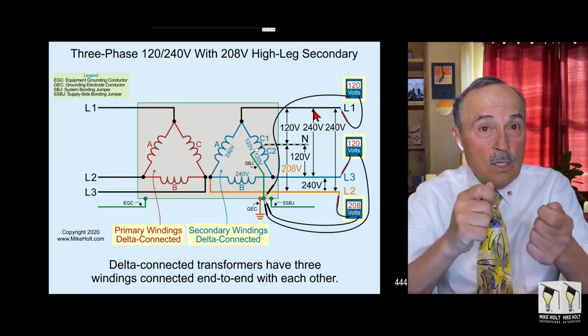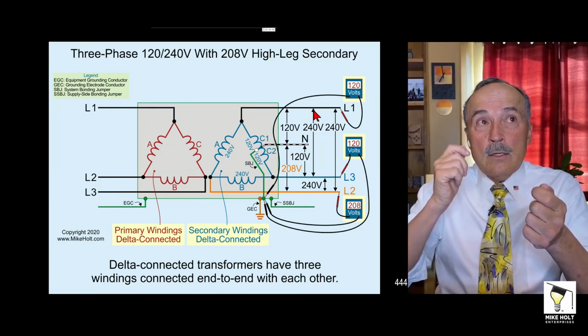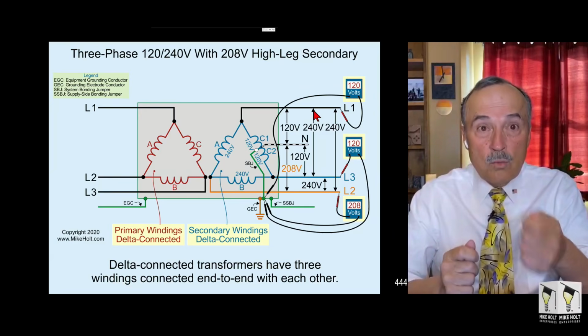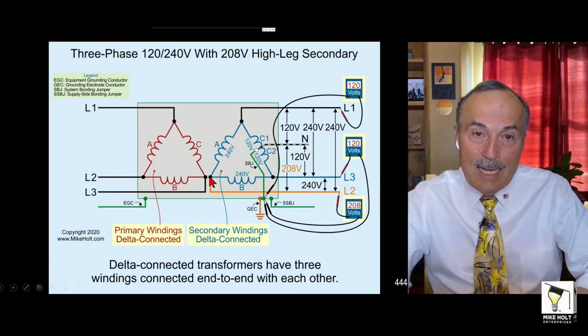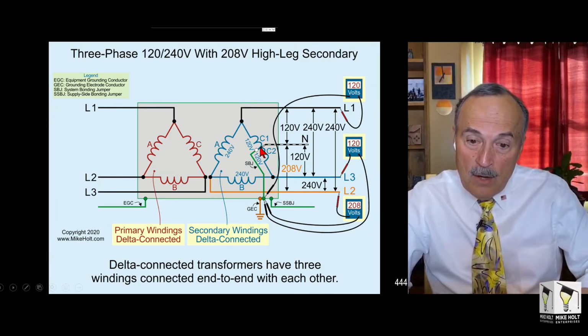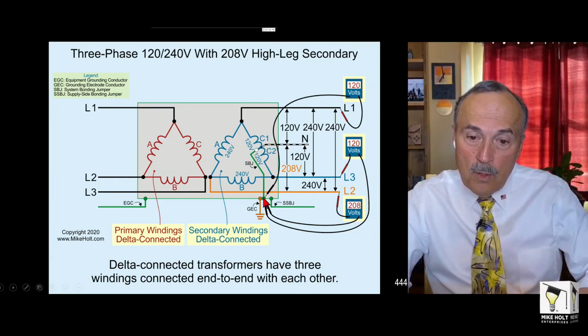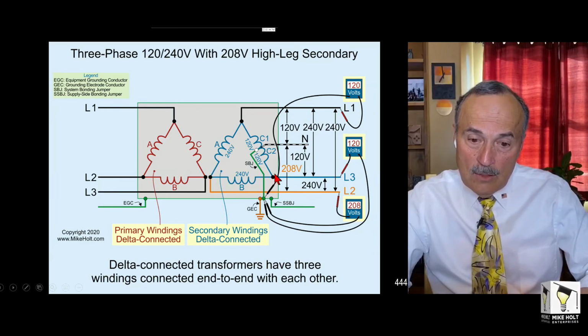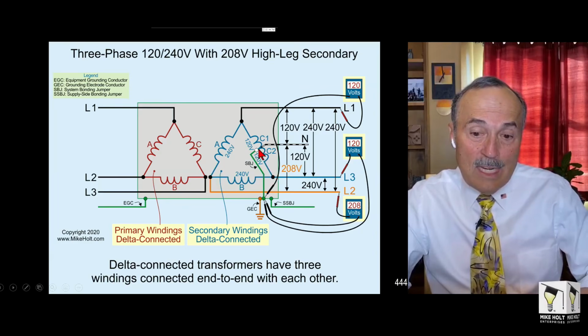Line 1, the neutral is 120. Line 3 to the neutral is 120. But the high leg is kind of hanging out here. From that reference point, which is where the neutral point is or where the ground point is, it's going to be 240 volts vectorially added with 120.